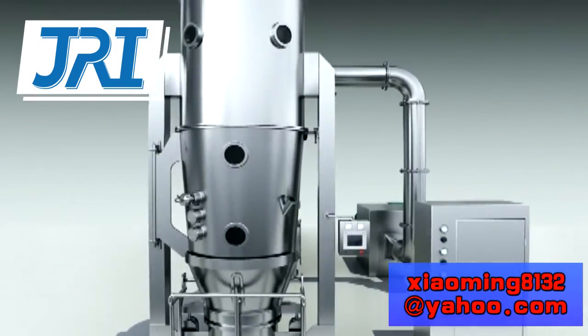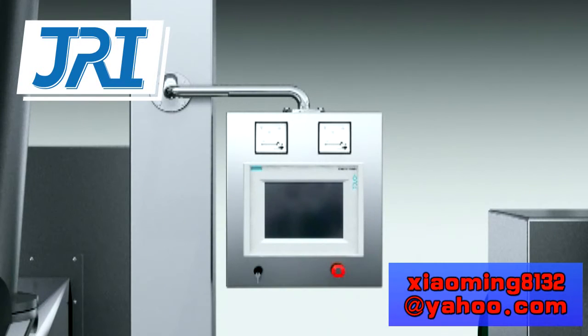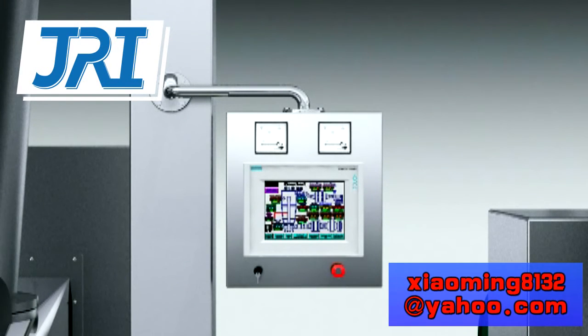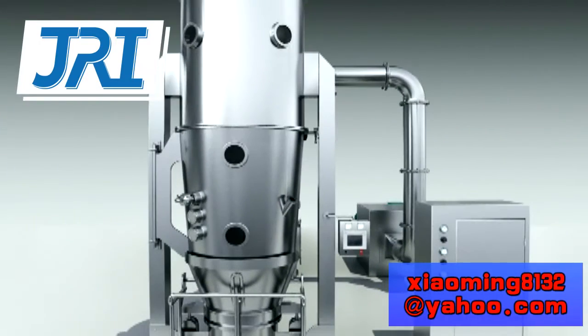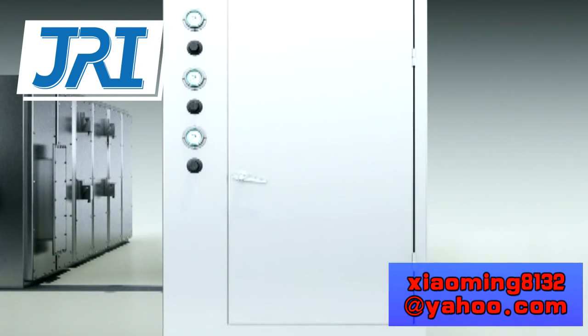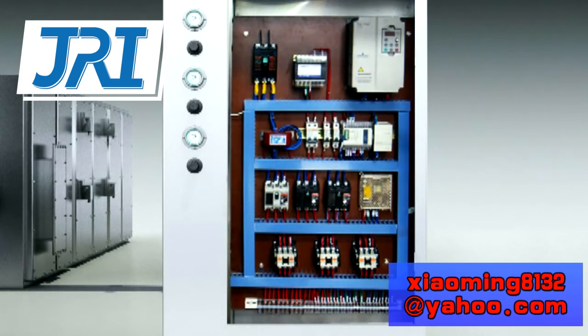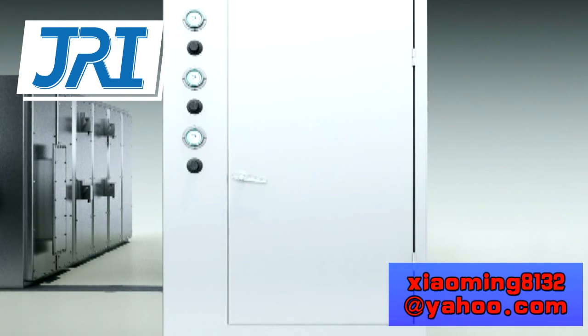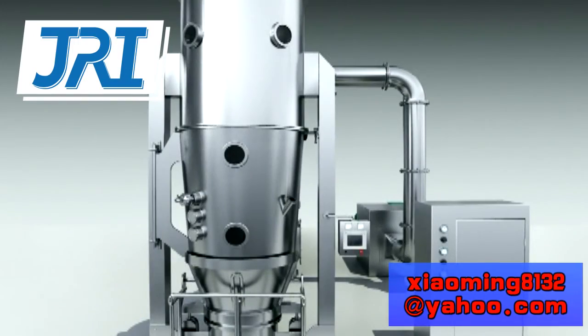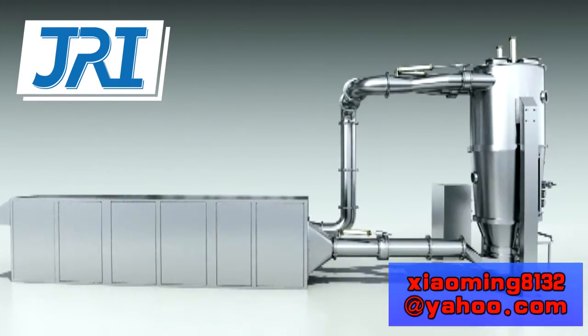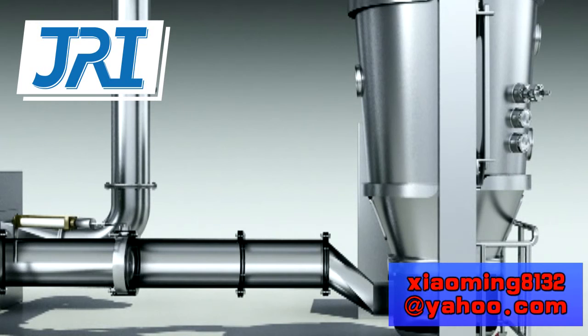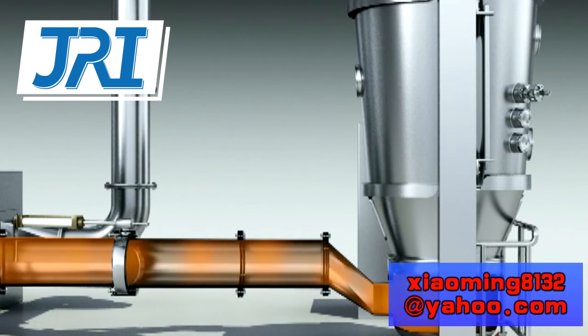Control system. 1. Siemens PLC and human machine interface are normally supplied for the control system. 2. Inverter is normally used for the suction fan, so to adjust the air velocity and pressure smoothly and save energy. 3. Air speed and humidity transmitters are normally used for this system, so to measure the inlet air speed, which might be converted to air velocity and humidity, or the humidity after the dehumidifier if applicable.